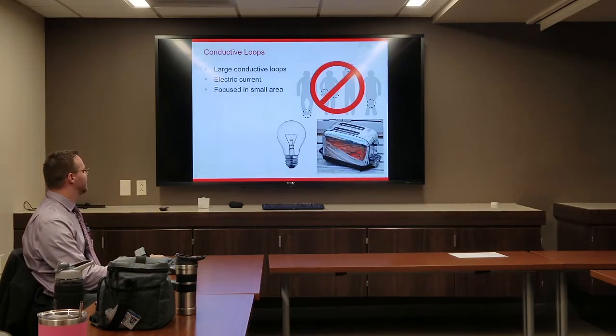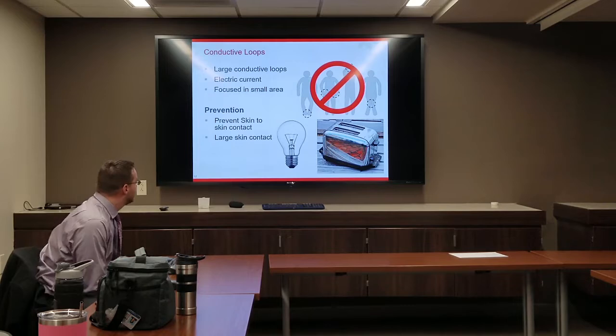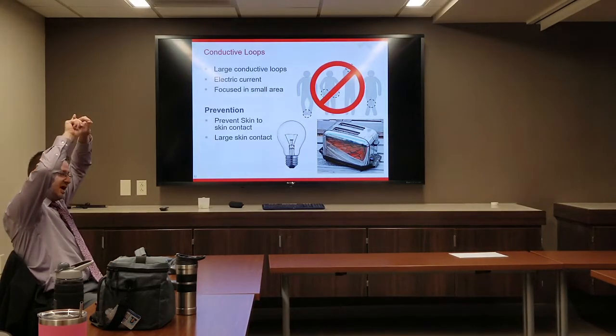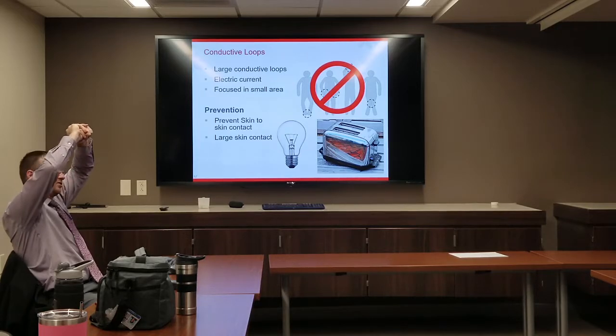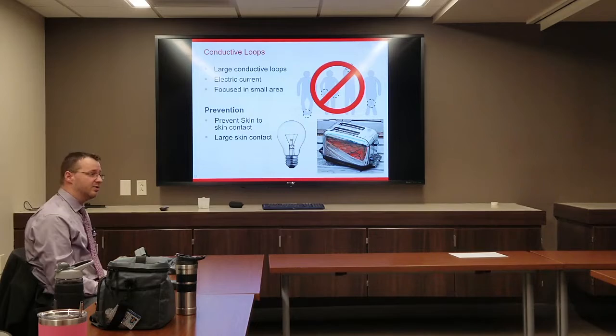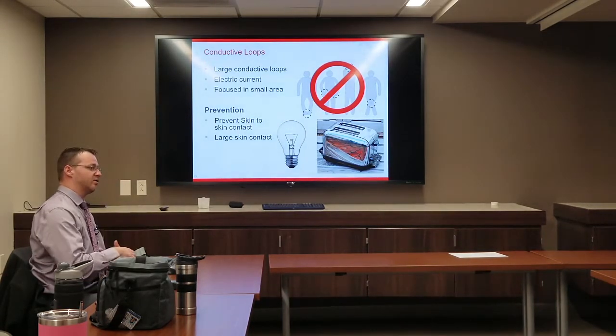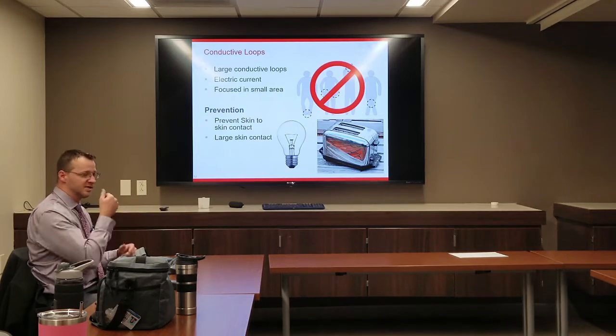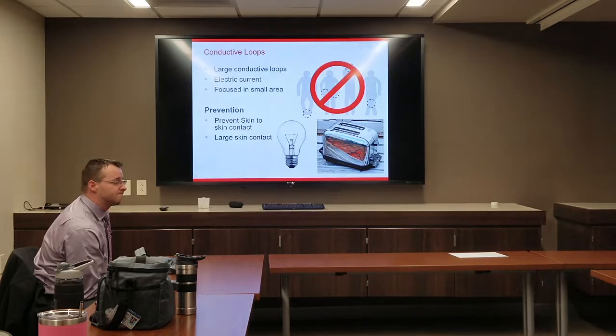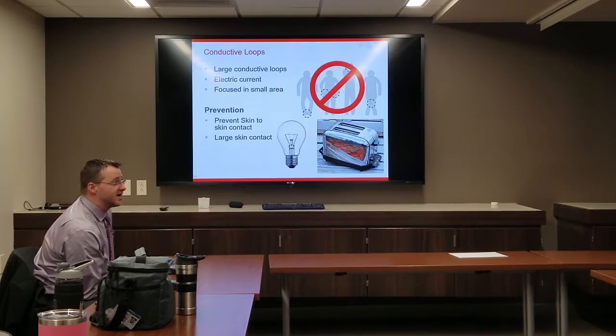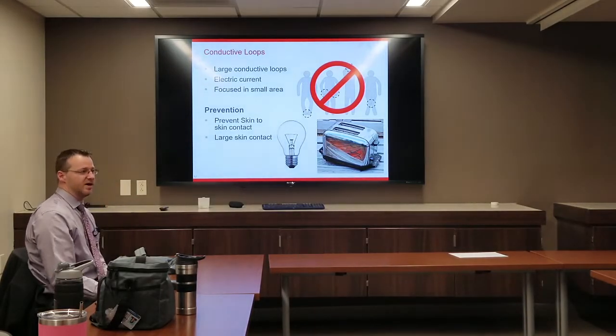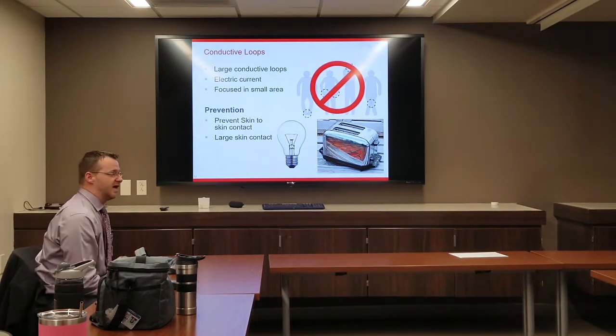To prevent conductive loop burns, prevent skin-to-skin contact. Also, if there is a large contact area, the energy is dissipated over that larger area and won't heat up in a focal spot — for example, fingertips just touching creates high risk, but gripping hands solidly disperses energy. Non-conductive clothing (scrubs) prevents the loop from forming, unless saturated with sweat making it conductive. The concept is similar to a light bulb filament — high resistance in a thin area gets very hot.